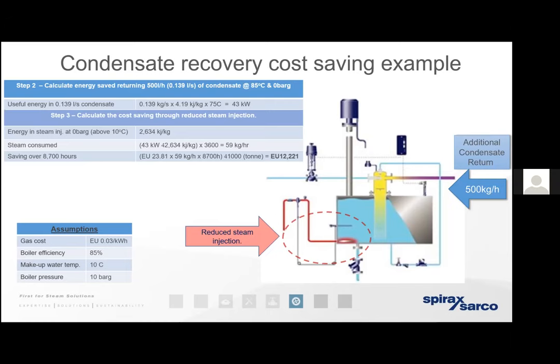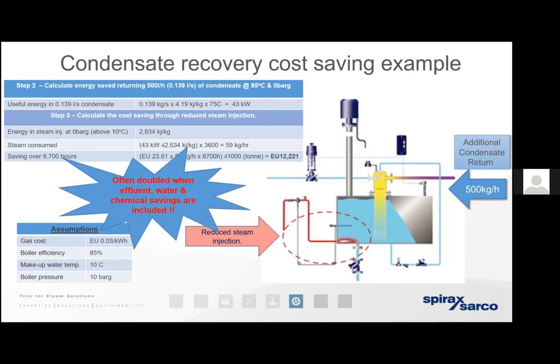If we can now get condensate back to the hot well at, say, 75 degrees, there will be far more energy in the feed water and we need far less direct steam injection to bring it to 85 degrees. In the case of raising raw water from 10 to 75 degrees by condensate return rather than relying on direct steam injection, it would save 59 kilograms of steam per hour, which over a year equates to over 12,000 euros. Remember, this is just for an increased return rate of 500 kilograms per hour — it's scalable to whatever you can recover. And that's just the energy savings.